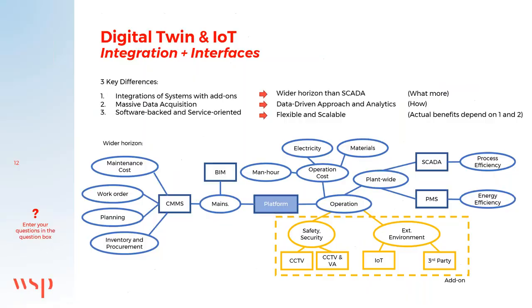When you integrate or interface so many things together, remember to do wise interface management. With so many systems integrated, you need to handle different challenges like I/O functions, data handshaking issues, and interoperability between systems. Identify what's monitoring only, what's operational, what's the data format, and what's the target for machine learning analysis — otherwise you integrate everything and just make the system complicated without any real function.